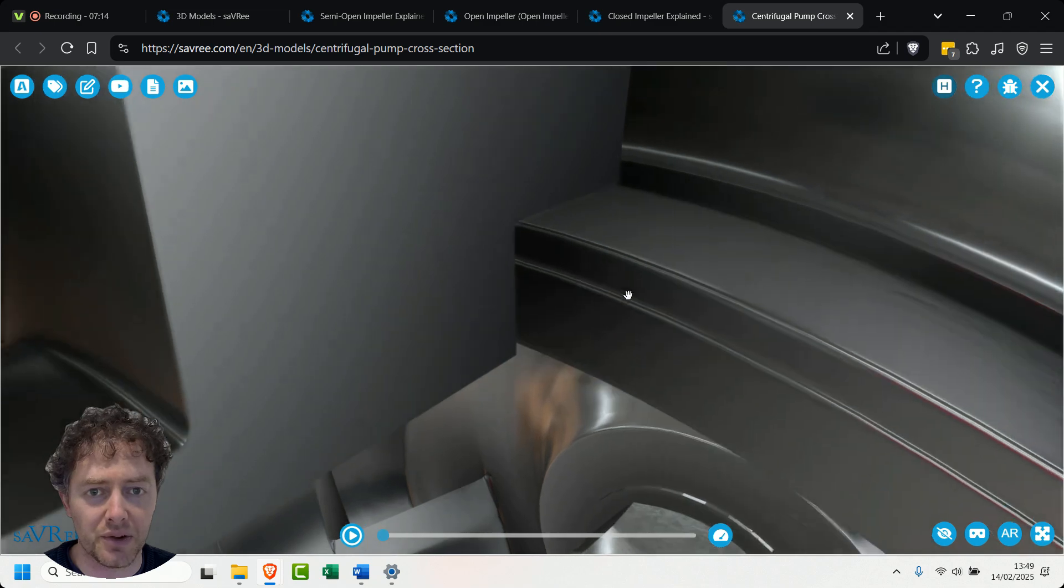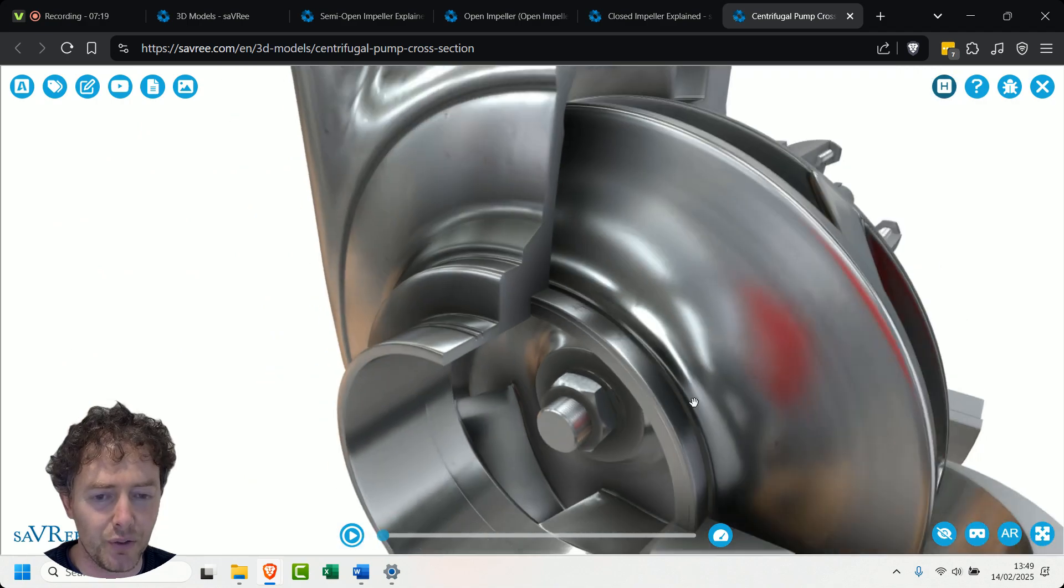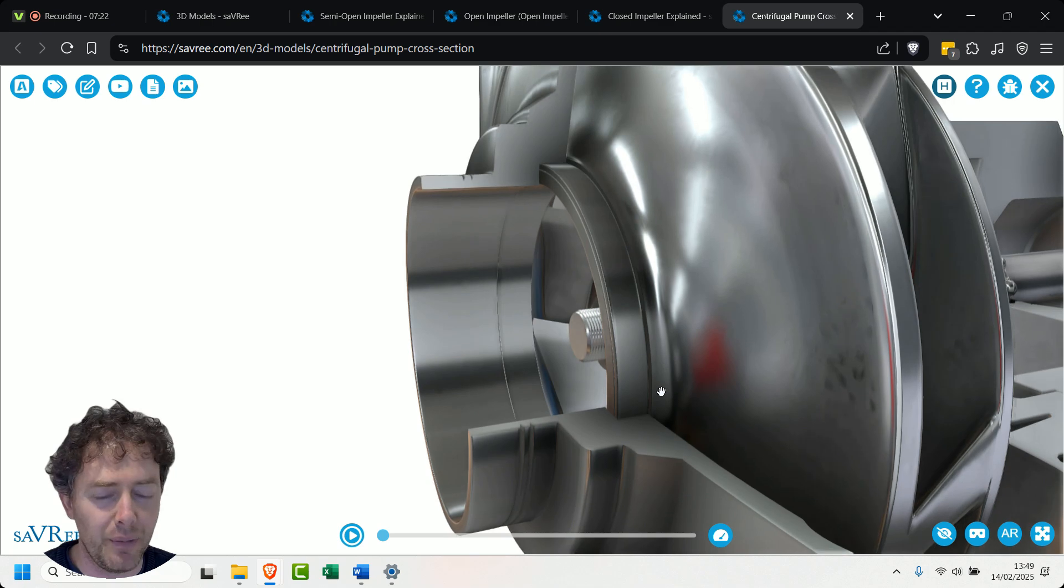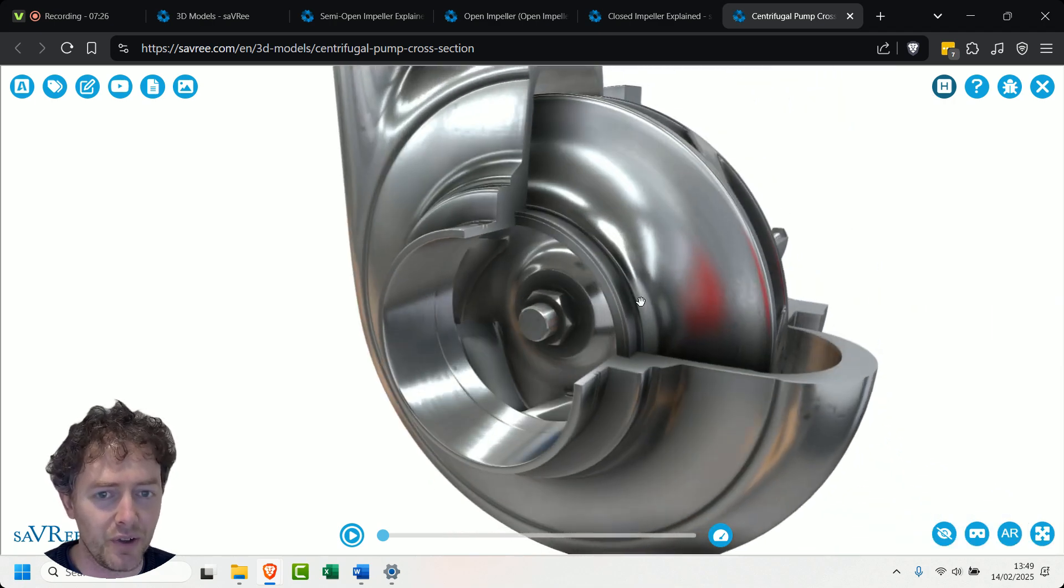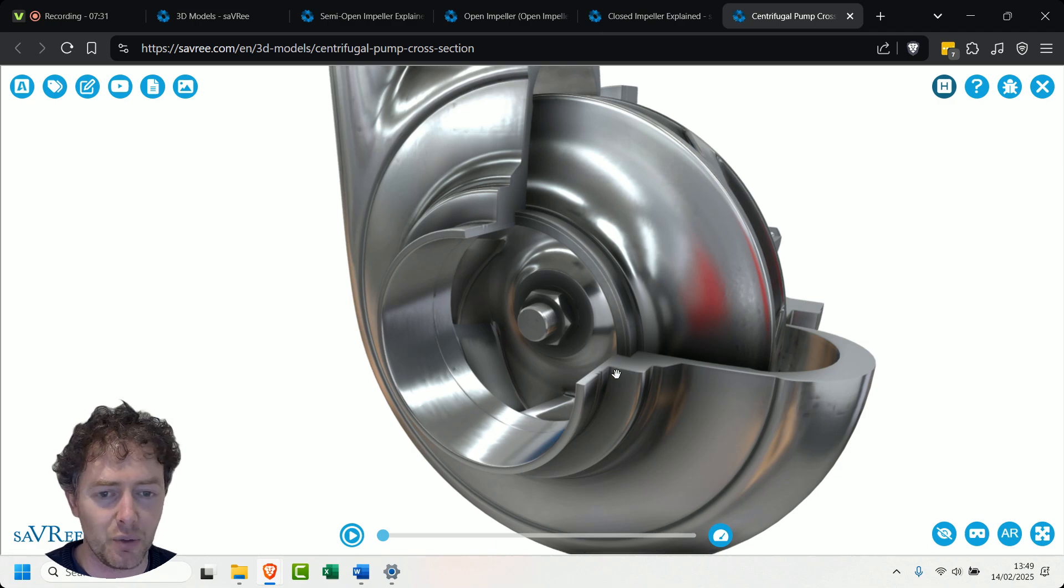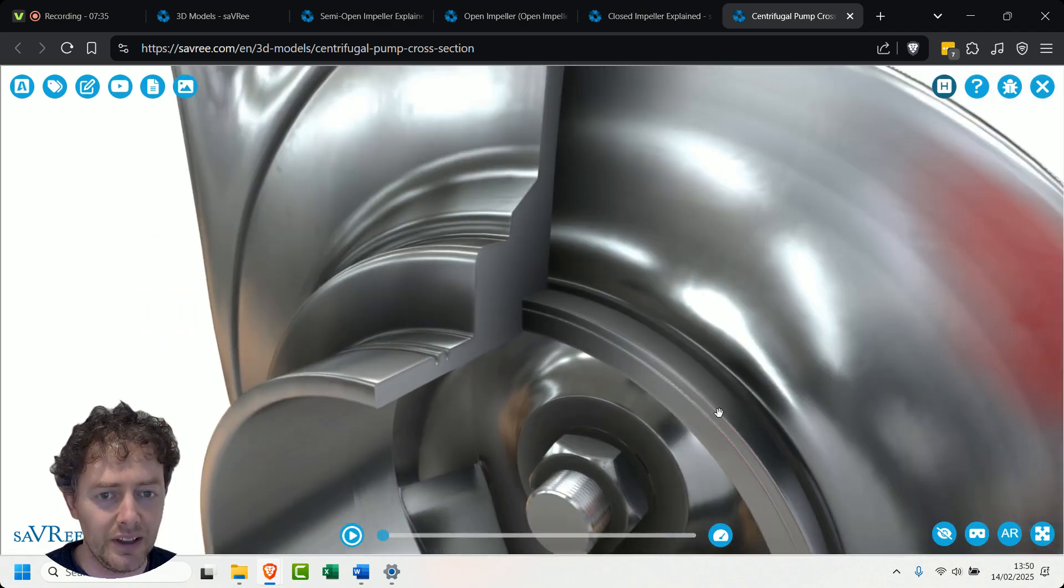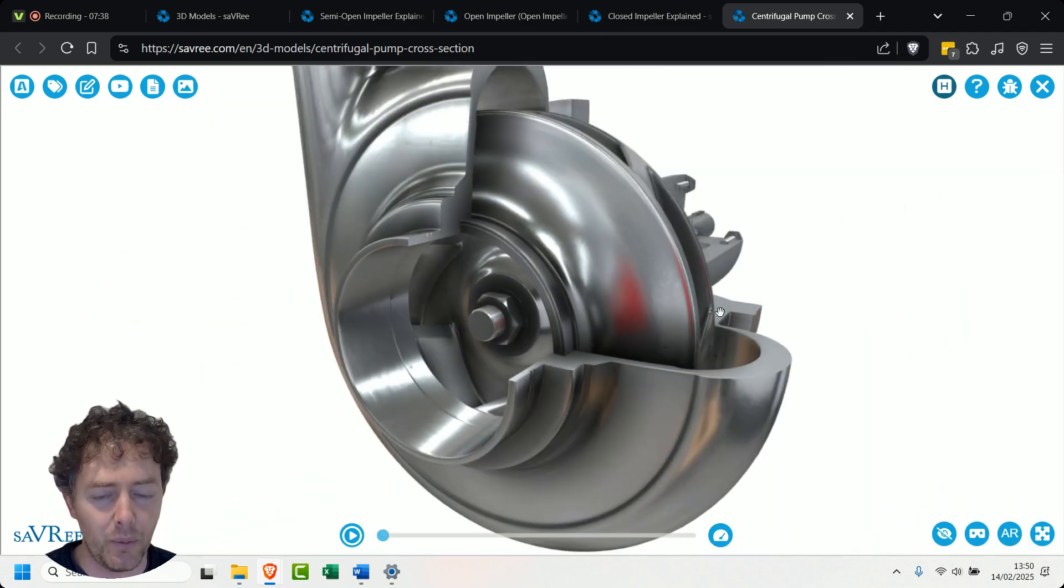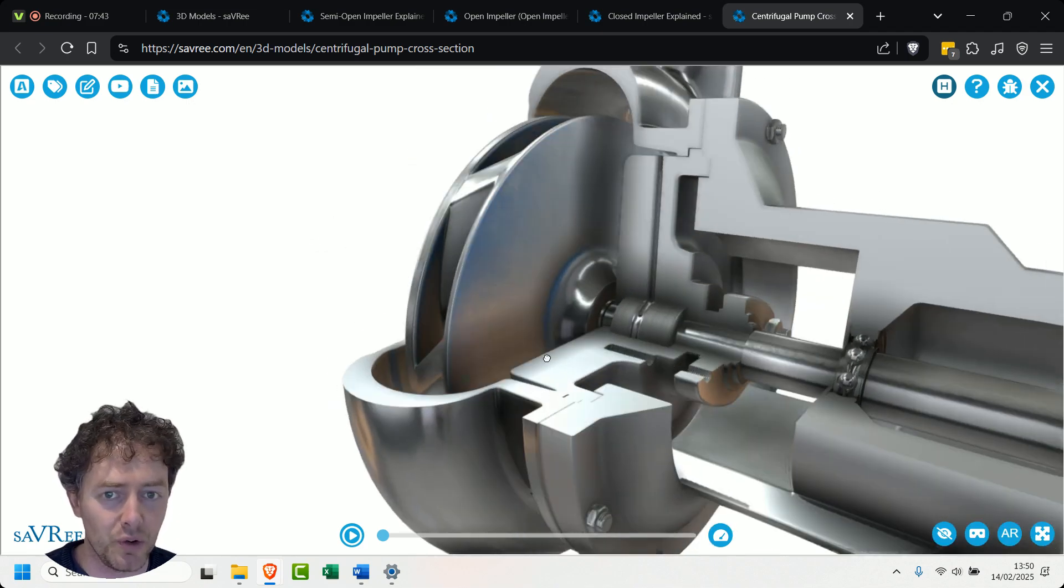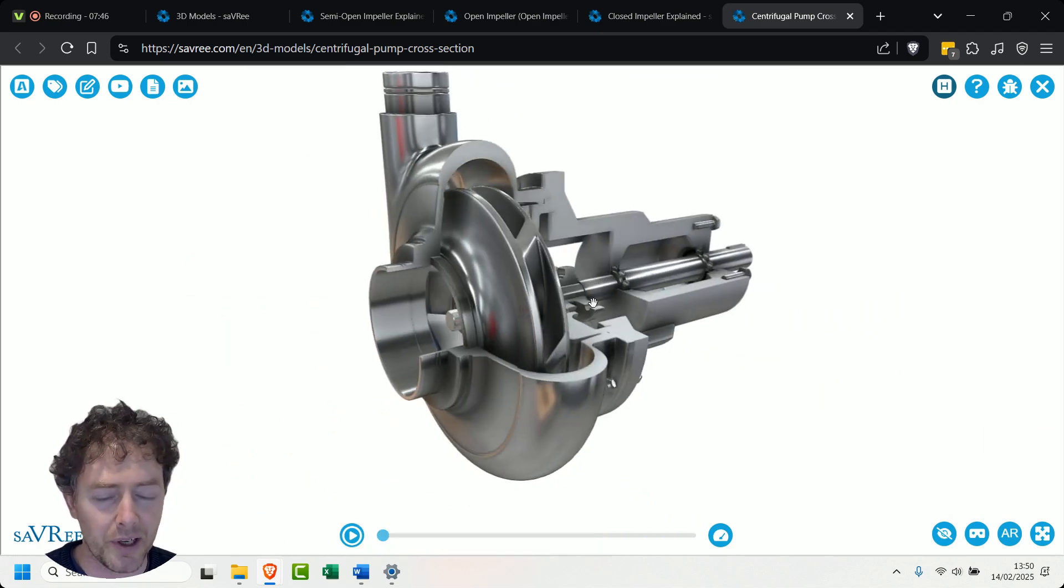If we zoom in here you'll see this wear ring, that's it where my mouse is. The reason you have that is because the pump, this overhung pump, it vibrates a bit, it moves around a lot, the impeller spins and we want to change the wear ring, we don't really want to change the whole impeller. Impellers cost a lot of money as does the volute casing so we'll add wear rings on the impeller and also on the casing itself and those will wear away over time rather than wear away the impeller or the volute casing which will cost a lot more money.